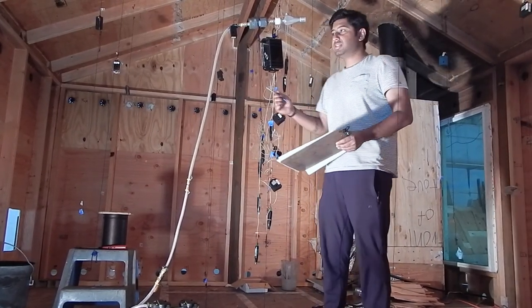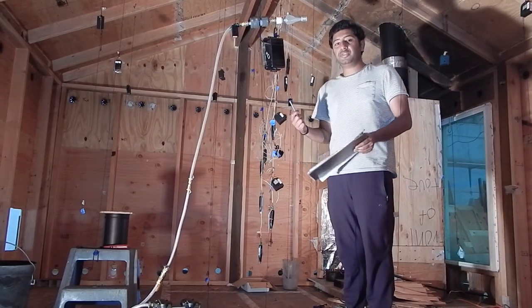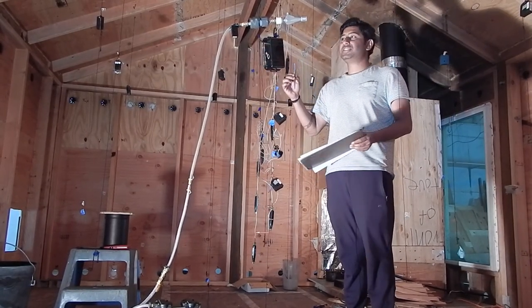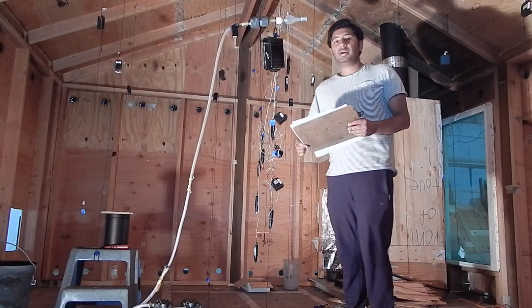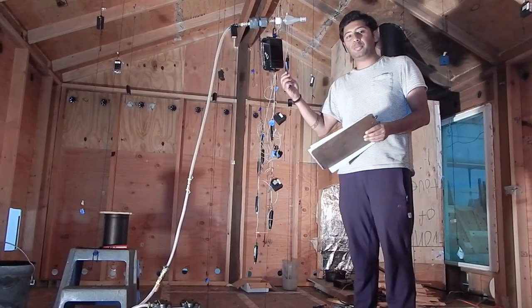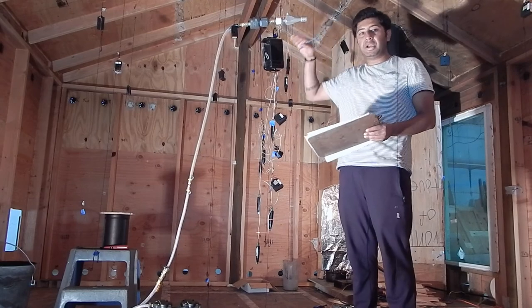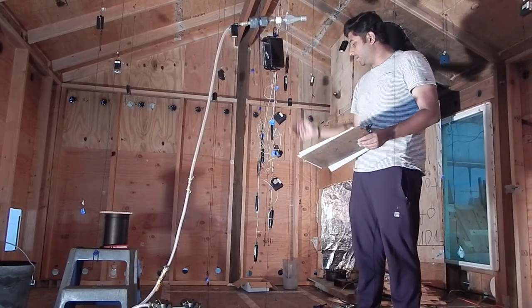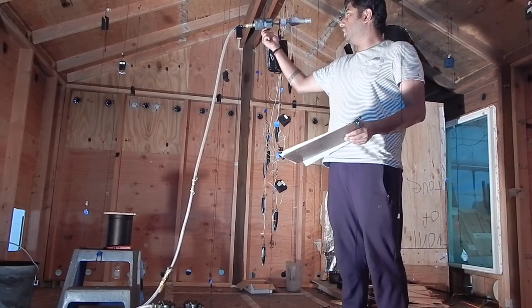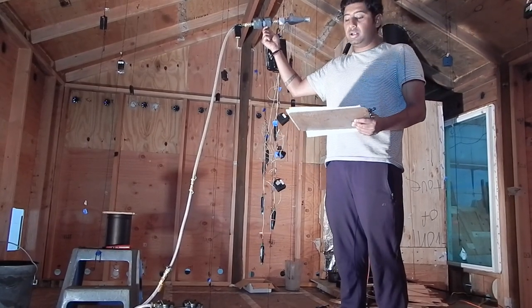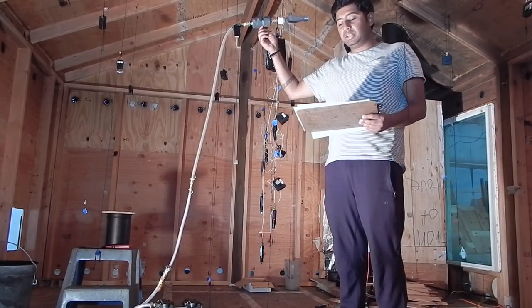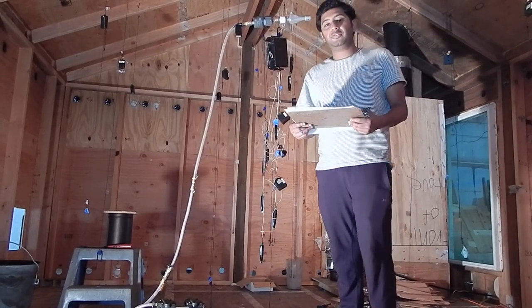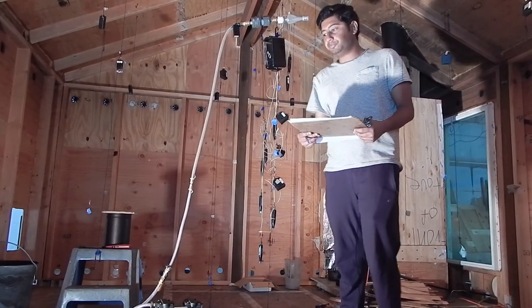This is the inside of our test kitchen where we have meticulously placed all these sensors to capture the concentration of PM2.5. We have made a horizontal grid and a vertical grid, and we are using a test filter to get the gravimetric calibration for a reference measurement of PM2.5.